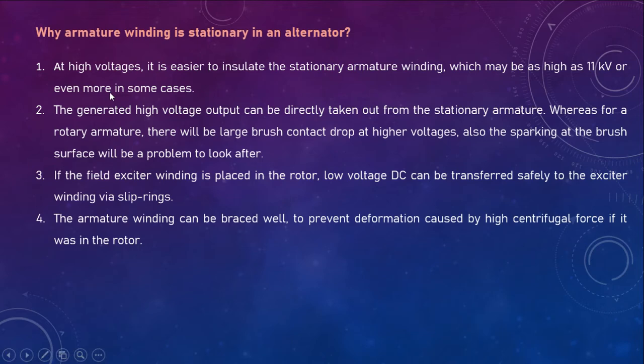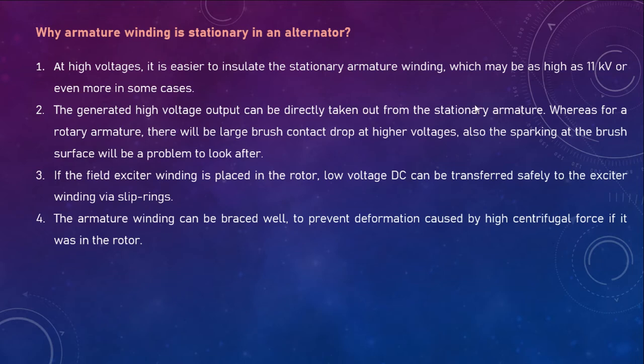The second advantage: the generated high voltage output can be directly taken out from the stationary armature. Since the stator is stationary and the armature winding is stationary in the stator, whatever output voltage is generated can be easily taken out. But if it were placed in the rotor and continuously rotating, it would be very difficult to take out the output power.